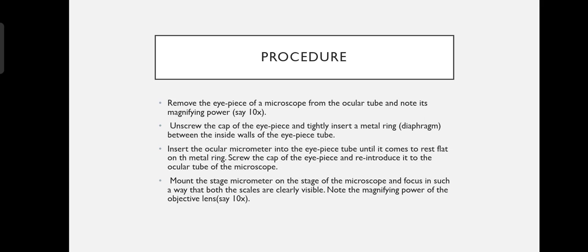It involves the following steps: remove the eyepiece of the microscope from the ocular tube and note its magnifying power. Then unscrew the cap of the eyepiece and tightly insert a metal ring between the inside wall of the eyepiece tube. Then insert the ocular micrometer into the eyepiece tube until it comes to rest flat on the metal ring. Screw the cap of the eyepiece and reintroduce it to the ocular tube of the microscope, and then mount the stage micrometer on the stage of the microscope and focus in such a way that both the scales are clearly visible.